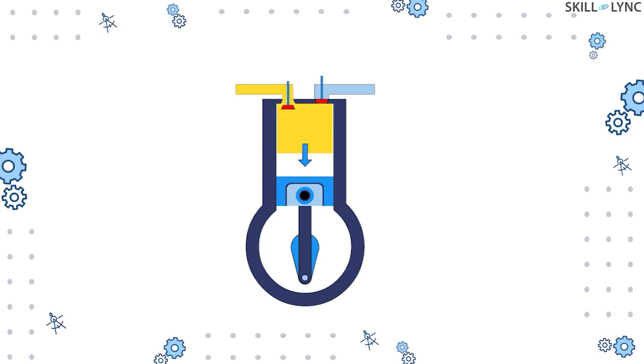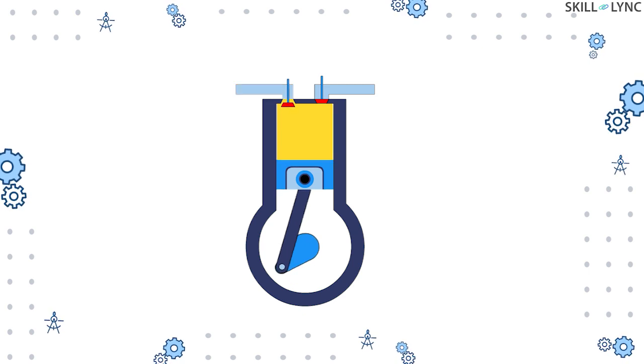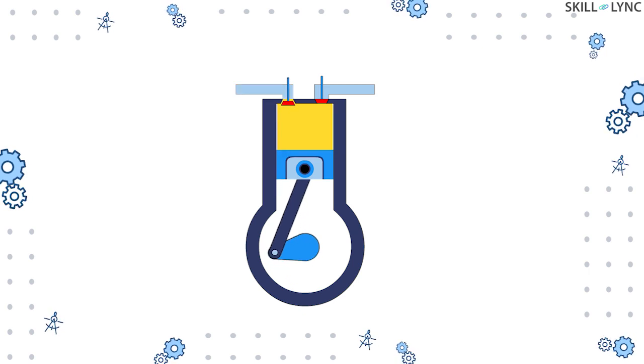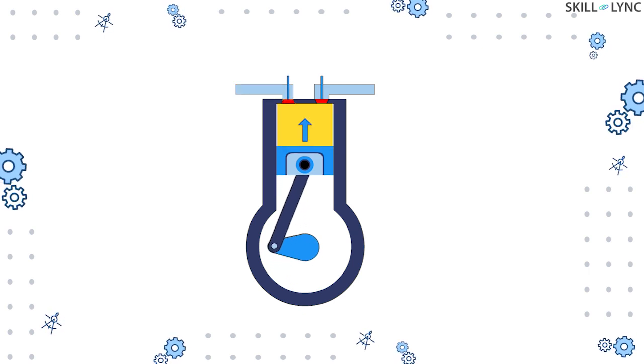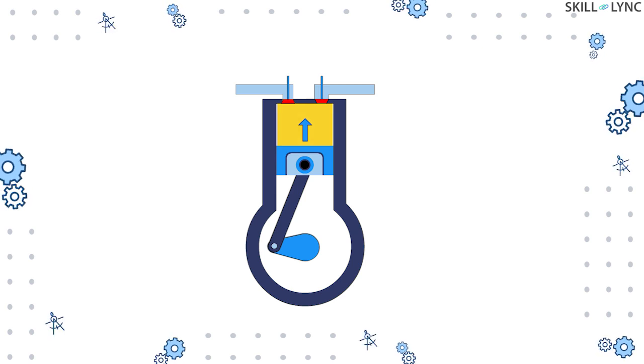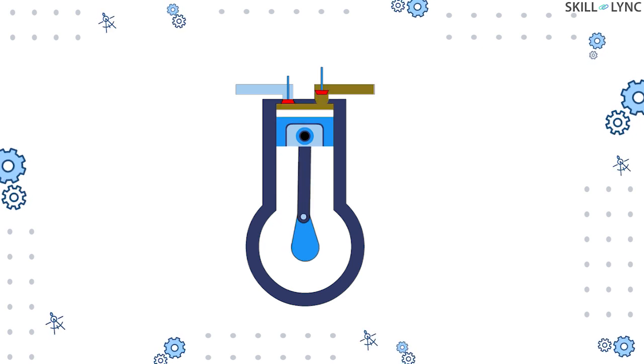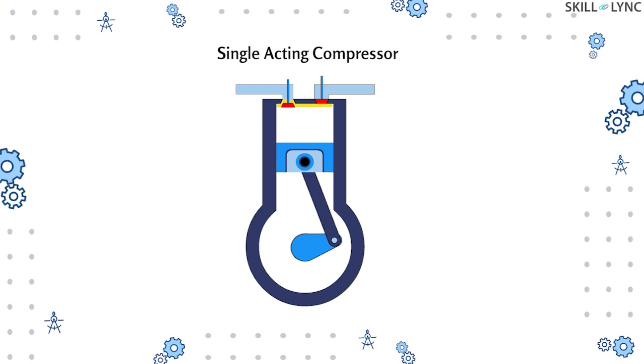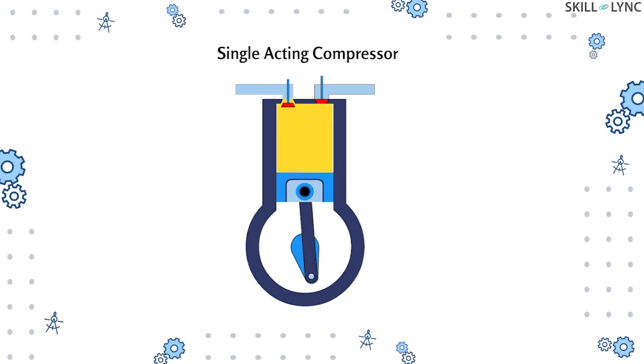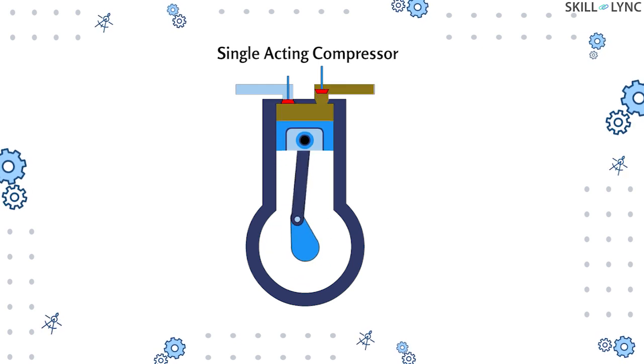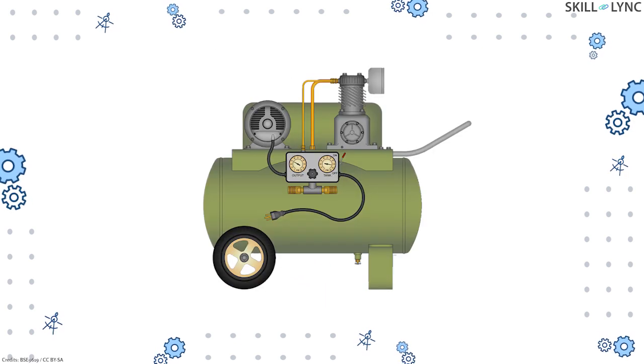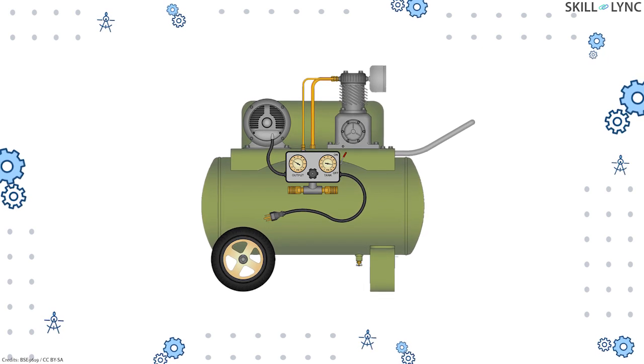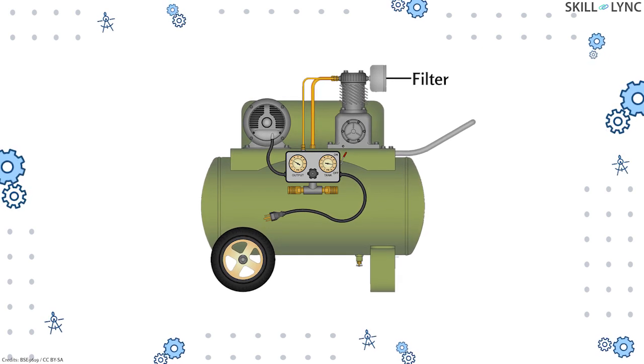Now when the piston moves up, it compresses the air. The increased pressure developed inside the cylinder opens the delivery valve and the compressed air is sent to the storage tank. This simple type of reciprocating compressor is known as a single acting compressor.